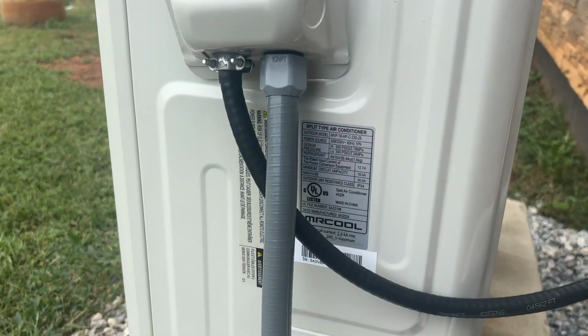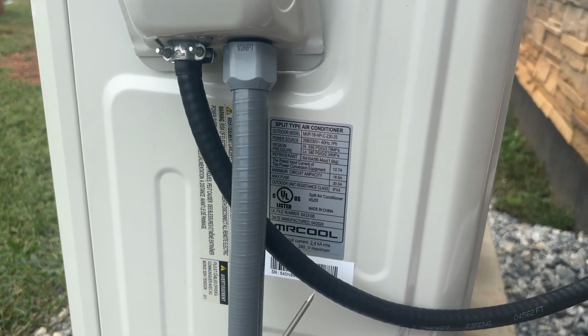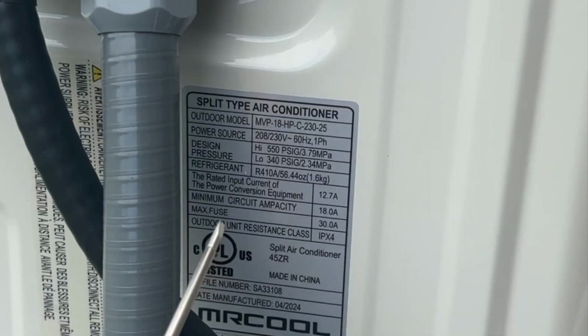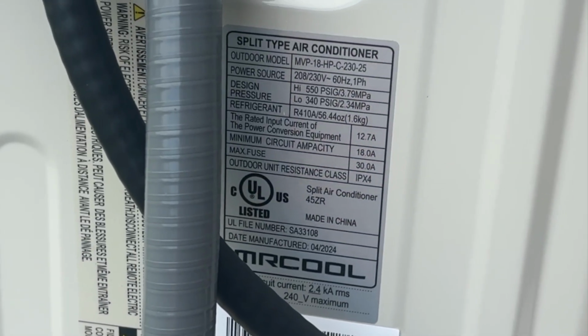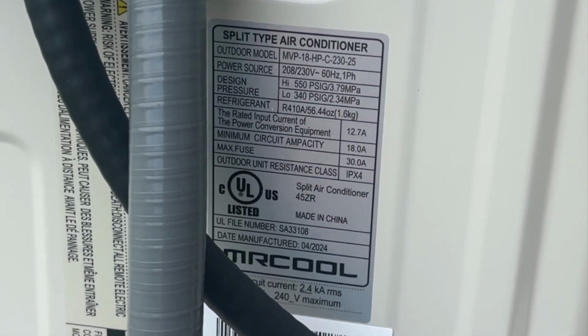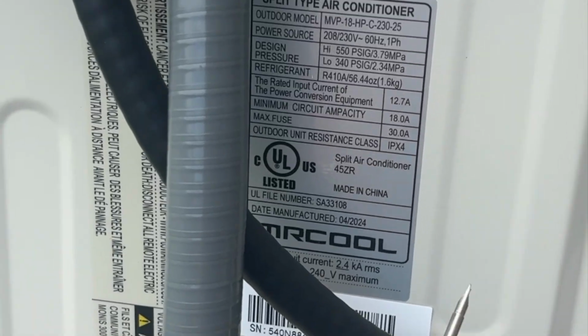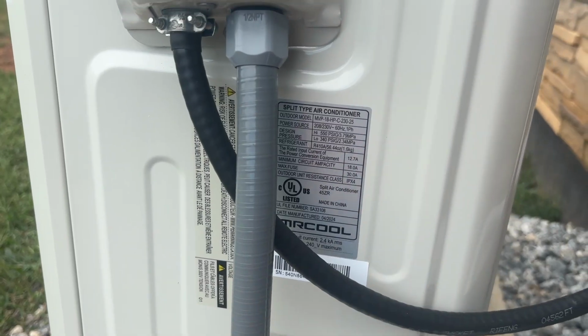Let's take a look at where the power comes into the outdoor unit first, and then we'll move to the indoor air handler. Your power requirements are going to be listed right on your outdoor unit, and you can see maximum fuse and minimum circuit ampacity. Those are the two important numbers for you. 30 amps is the max fuse.